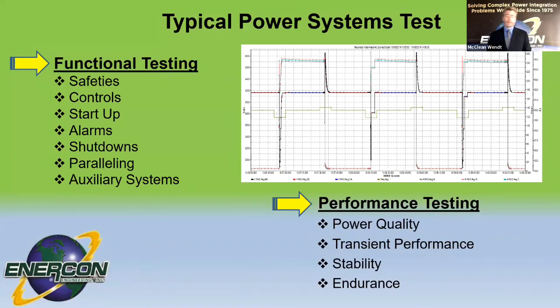And then we'll want to go through all of the controls to make sure that all the non-operating controls are displaying correctly, reporting the status of the auxiliary systems correctly, all the communications, all the devices are communicating properly. And then we're able to move into startup. So when we say startup, that's going to be when we start up the engine generator for the first time, or start up the system for the first time.